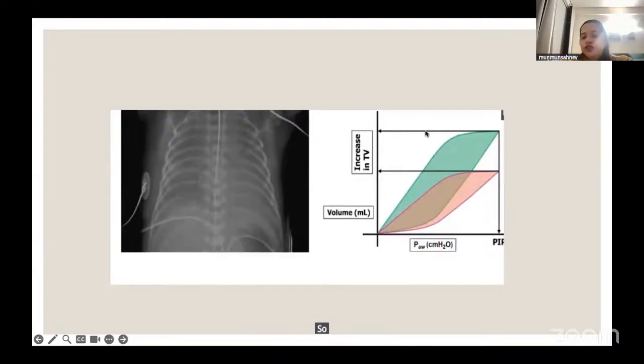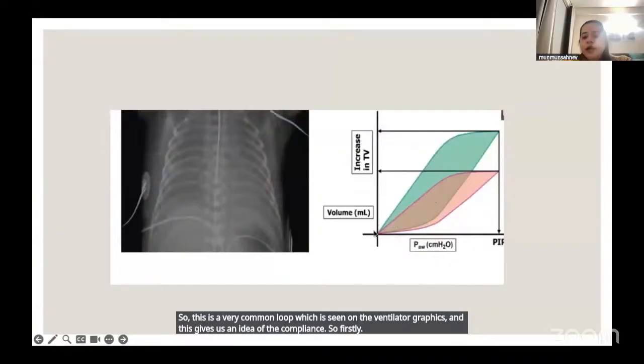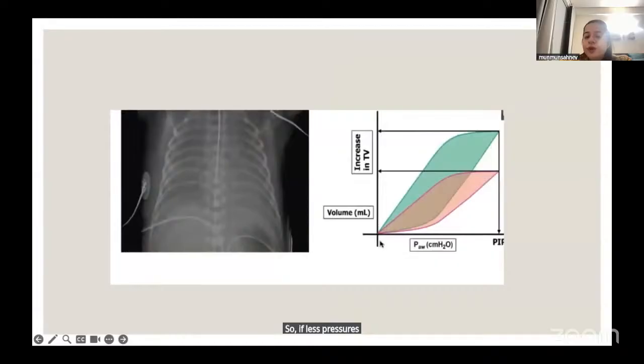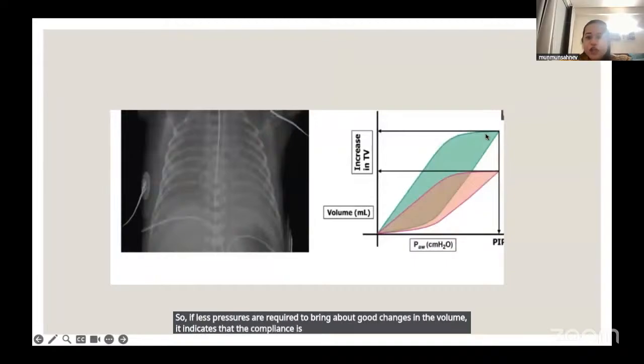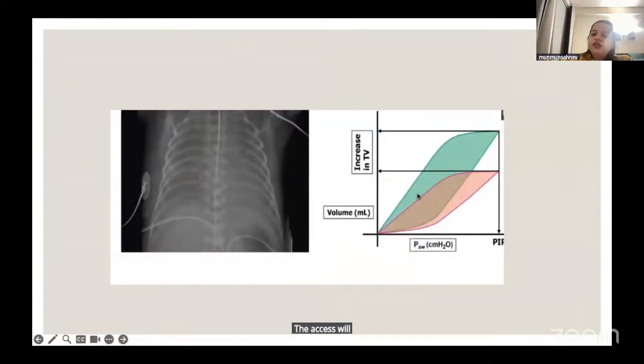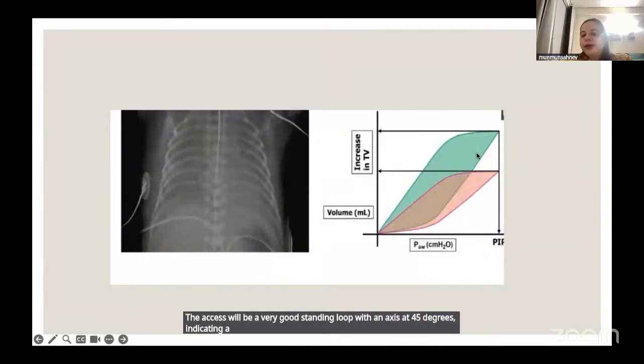So this is a very common loop which is seen on the ventilator graphics, and it gives us an idea of the compliance. So firstly, what is compliance? Compliance is the change in volume brought about by a unit change in pressure. So if less pressure is required to bring about good changes in the volume, it indicates that the compliance is good. If a pressure of 1 centimeter of water leads to a 1 ml increase in the tidal volume, the loop will be a very good standing loop with an axis at 45 degrees, indicating a normal lung compliance.